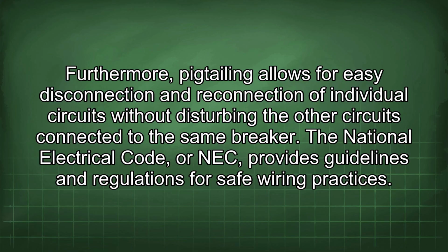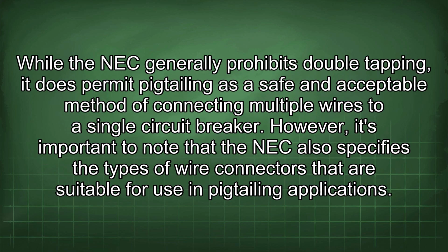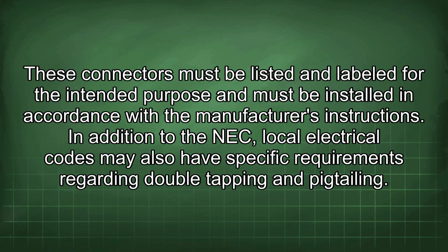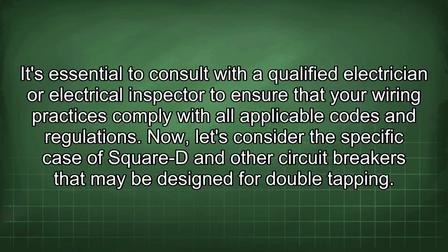The National Electrical Code, or NEC, provides guidelines and regulations for safe wiring practices. While the NEC generally prohibits double tapping, it does permit pigtailing as a safe and acceptable method of connecting multiple wires to a single circuit breaker. However, it's important to note that the NEC also specifies the types of wire connectors that are suitable for use in pigtailing applications. These connectors must be listed and labeled for the intended purpose and must be installed in accordance with the manufacturer's instructions. In addition to the NEC, local electrical codes may also have specific requirements regarding double tapping and pigtailing. It's essential to consult with a qualified electrician or electrical inspector to ensure that your wiring practices comply with all applicable codes and regulations.